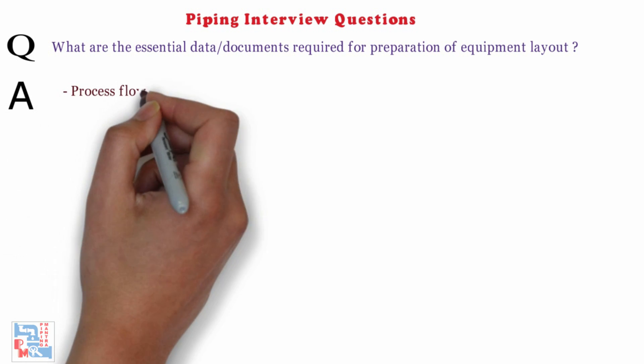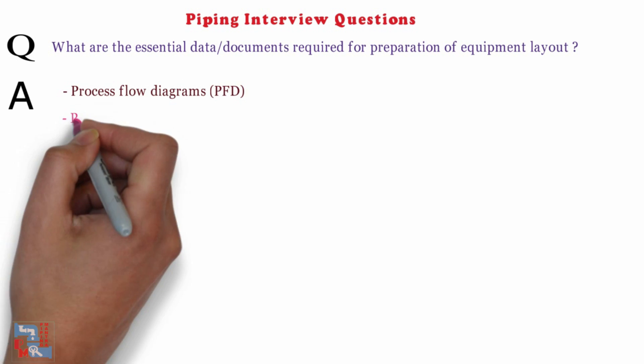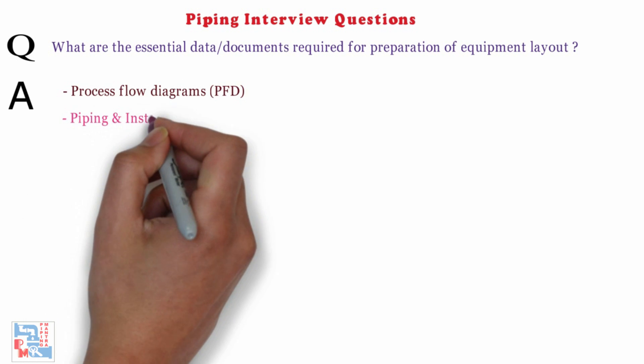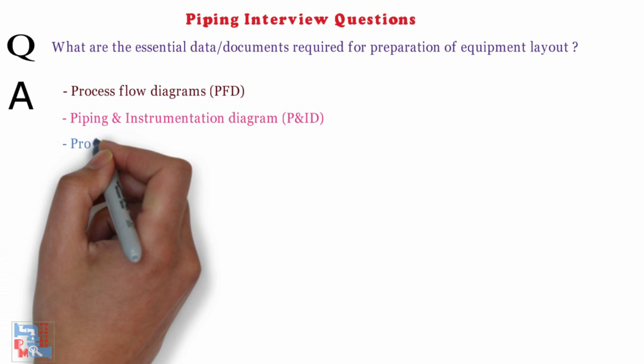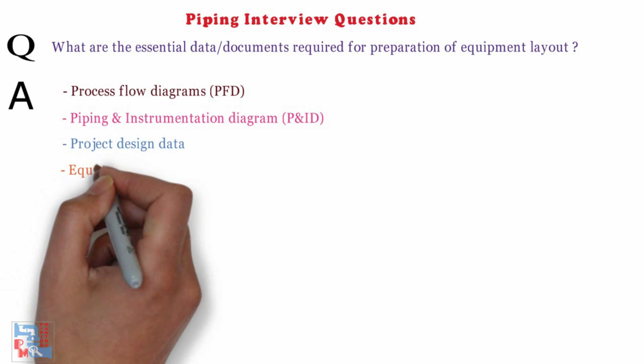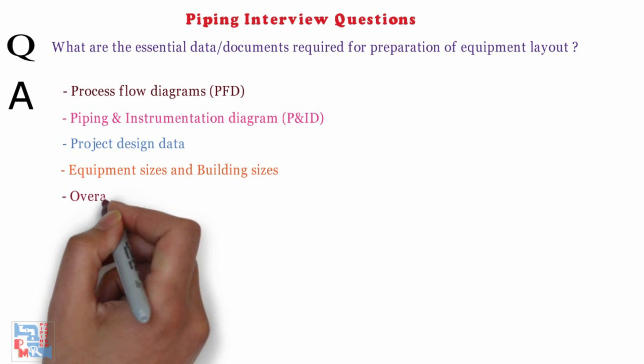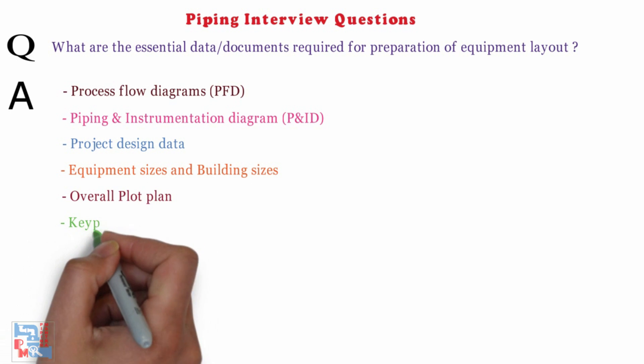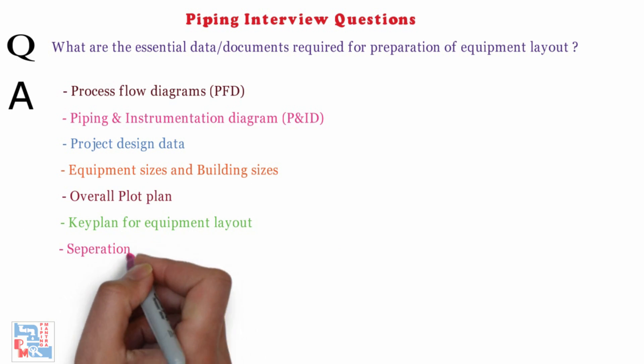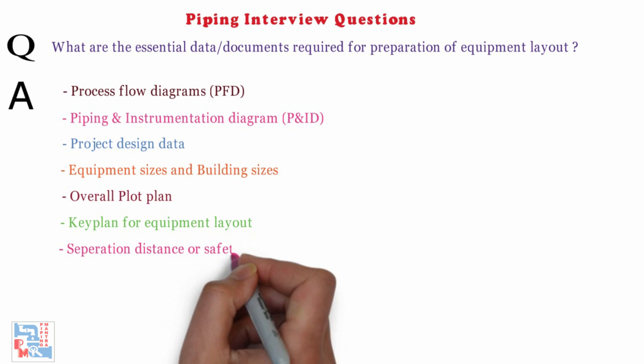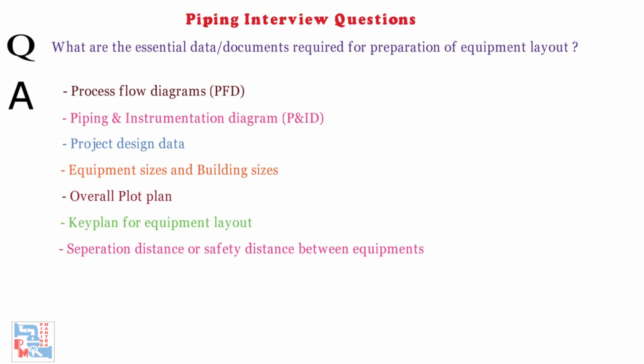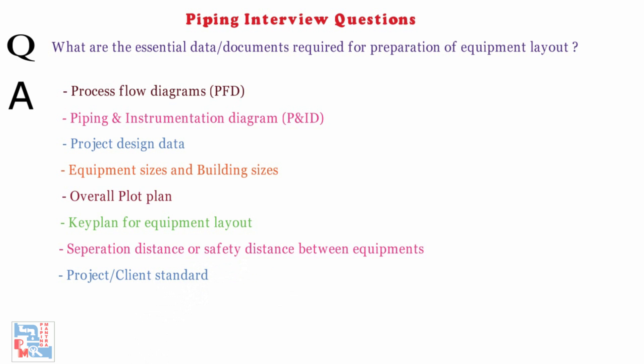Next, what are the essential data or documents required for preparation of equipment layout? The essential data or documents required are as follows. Process flow diagrams i.e. PFDs, Piping and Instrumentation diagrams i.e. P&IDs, Project design data, Equipment sizes and building sizes, Overall plot plan, Key plan for equipment layout, Separation distance or safety distance between equipments, Project and client standard. You can refer our video on equipment layouts also.